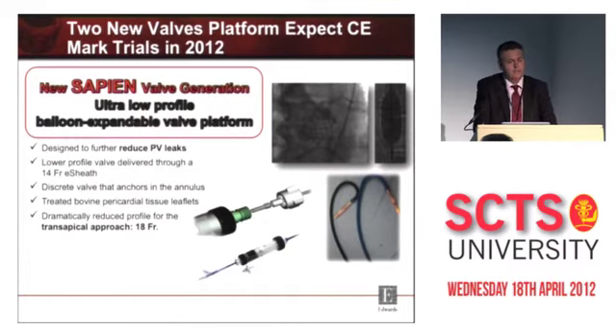Expect to start the CE mark trial in 2012. The new SAPIEN valve generation, which is almost what we can say is SAPIEN 3, is an ultra-low profile balloon expandable valve platform. The goal is to find a way to reduce paravalvular leak with this new design, to lower the profile to deliver this valve through 14 French sheaths, but also to reduce the profile on the transapical approach to 18 French. We also would like to continue to use the treated bovine pericardial tissue leaflets, as we believe, for durability.